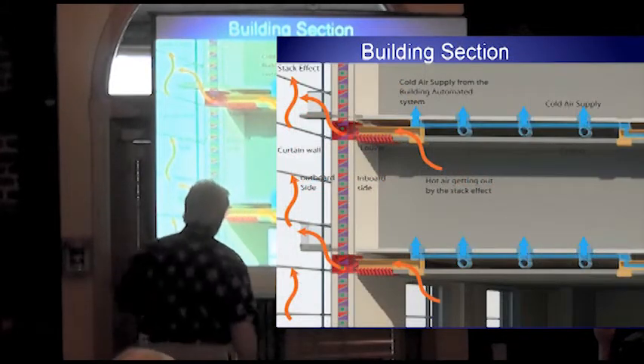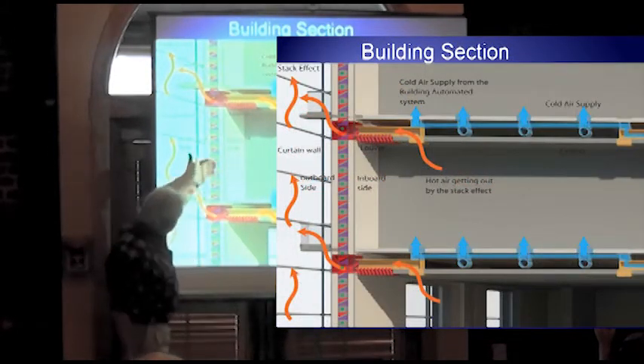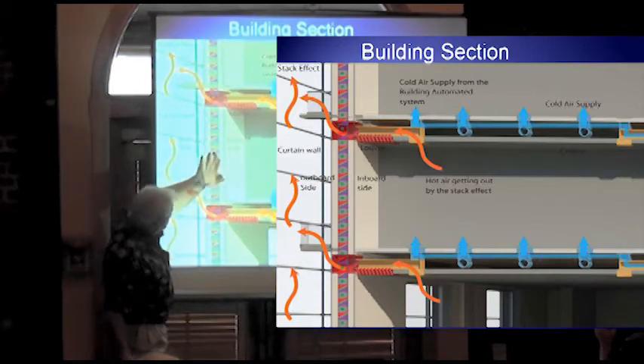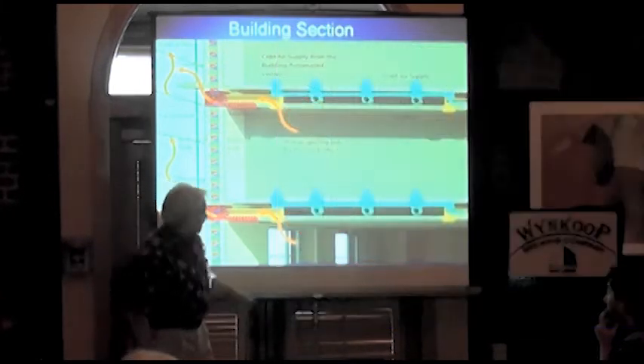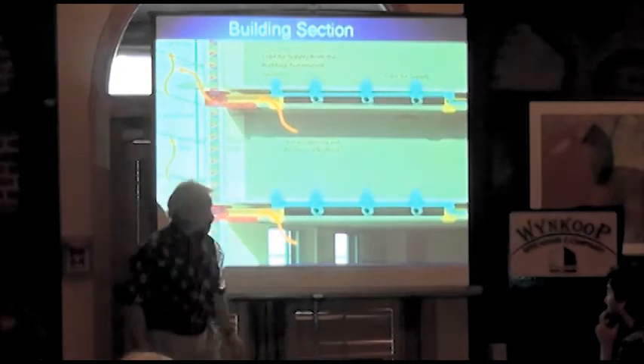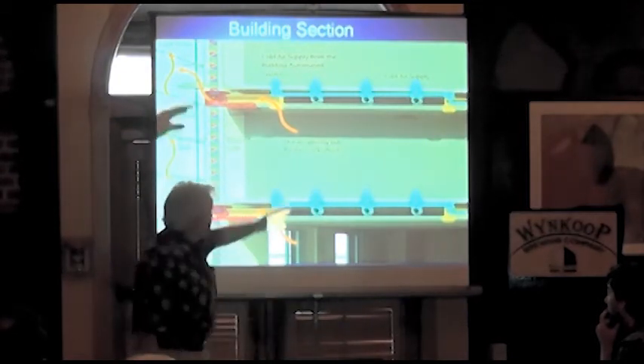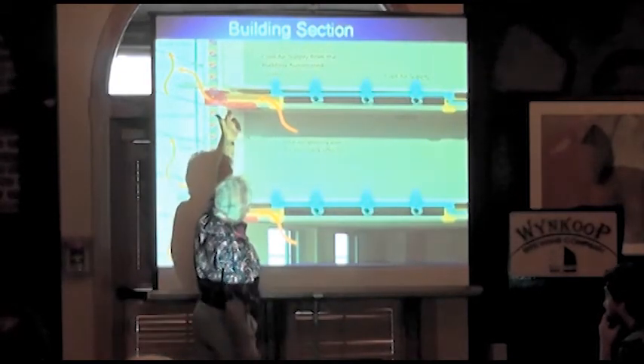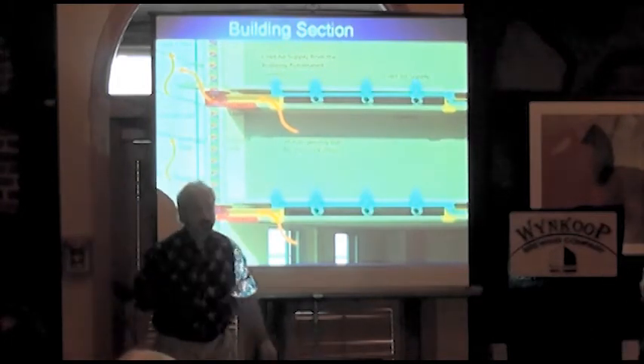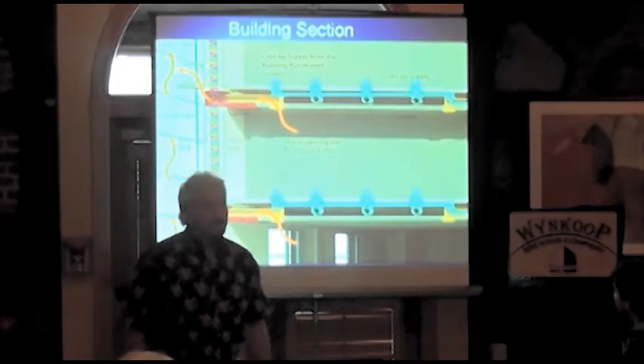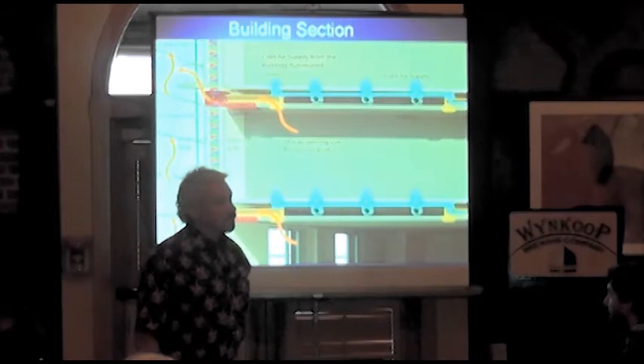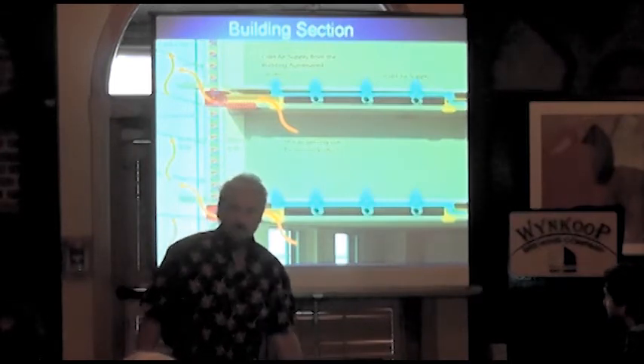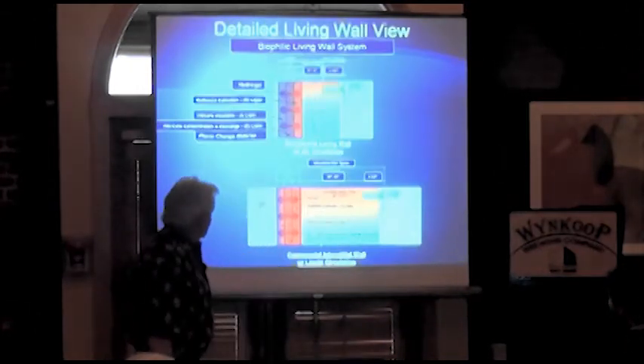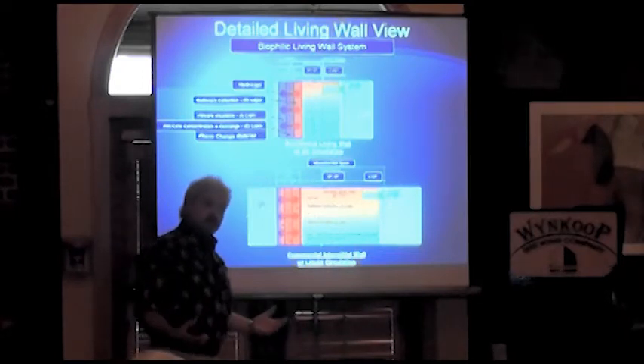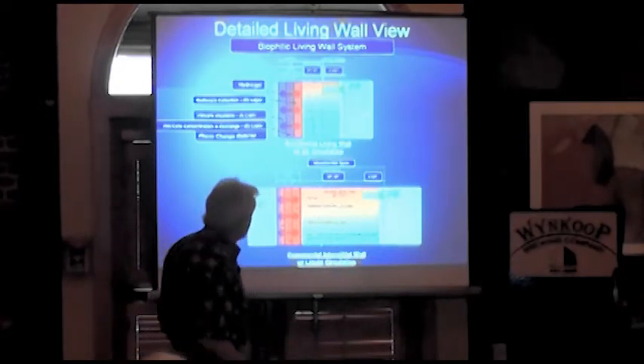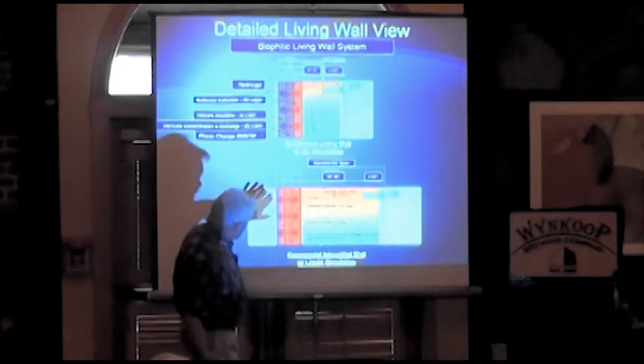Here's a zoomed in version of it. We're back into this living wall here. We're going to keep zooming in and taking a look at this wall, the business end of what we're talking about. So cold air supply through these interstitial floor systems, exhaust from below through the perimeter, connected directly into the interstitial wall. We're able to produce more than three times as much volume of air movement through the interstitial wall than we need. So the movement of air through these spaces is not the issue so much as the control of it.